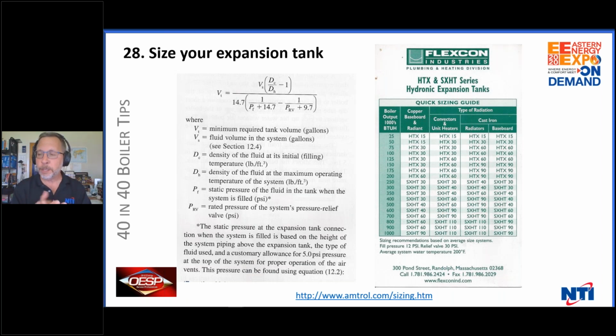If you go to www.amtrol.com, they actually have a sizing program that lets you size your tank in seconds. You need to know the water volume, you need to know the BTU, plug it in, know your temperature. You know that after the water gets to 130, it expands much greater. If your system's only going to be 130 down, you might be able to get away with a smaller tank. You can never oversize a tank, but you can undersize a tank. Do it right the first time.